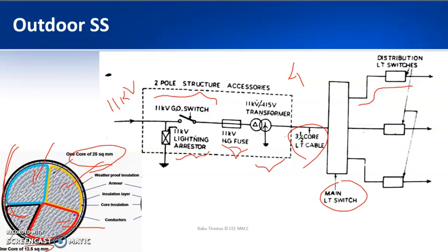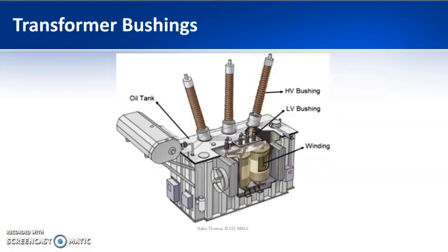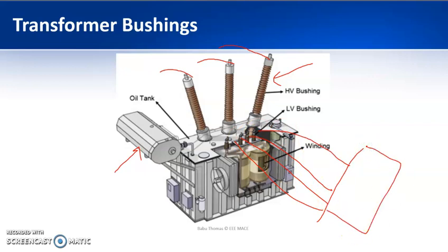Now we will see certain parts of this gang operated switch, the horn gap fuse and the transformer bushings in the next slides. So this is just indicating a transformer. The transformer will have an oil tank for cooling purposes. Then the major thing we need to focus on is the bushings. So this is a bushing. This is a high voltage bushing and this one is a low voltage bushing. The 11 kV supply from your horn gap fuse will come to these high voltage bushings, and you will take your LT cable, a 3.5 core cable, from these 4 terminals, and this is taken to the LT switchboard.